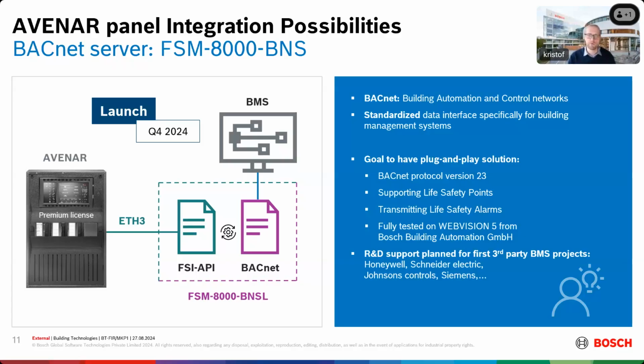We are using the BACnet protocol 23, and we are supporting the life safety points, and we are also transmitting life safety alarms. So in contrast to OPC, BACnet has really everything standardized, so you don't need to make this conversion table. It is fully tested on Web Vision 5 from our colleagues of Bosch Building Automation. But of course, every supplier of BMS system can have maybe a different flavor. Perhaps they are not using life safety points and life safety alarms.